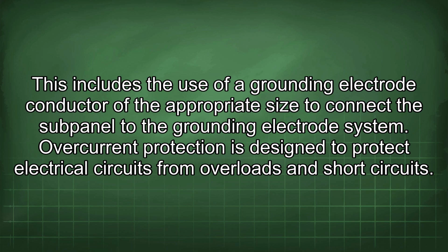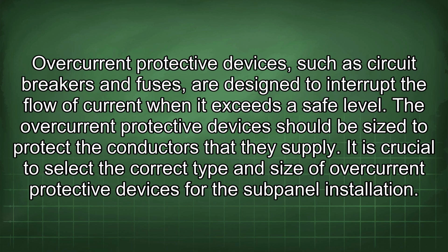Overcurrent protection is designed to protect electrical circuits from overloads and short circuits. Overcurrent protective devices, such as circuit breakers and fuses, are designed to interrupt the flow of current when it exceeds a safe level. The overcurrent protective devices should be sized to protect the conductors that they supply. It is crucial to select the correct type and size of overcurrent protective devices for the subpanel installation.